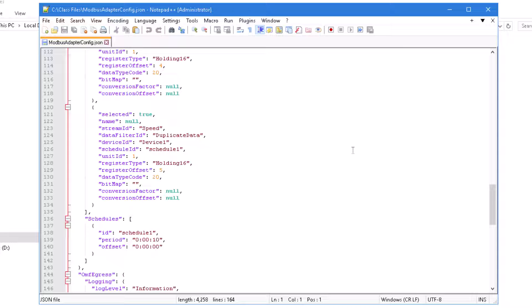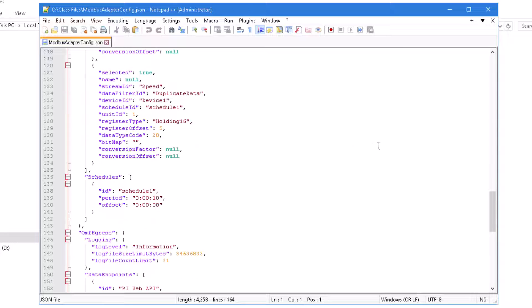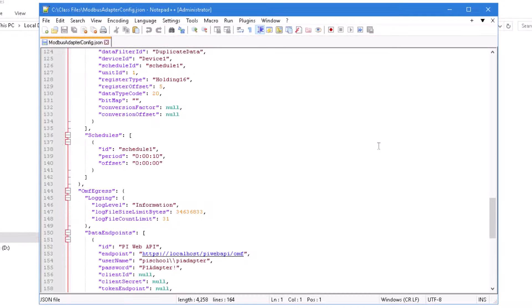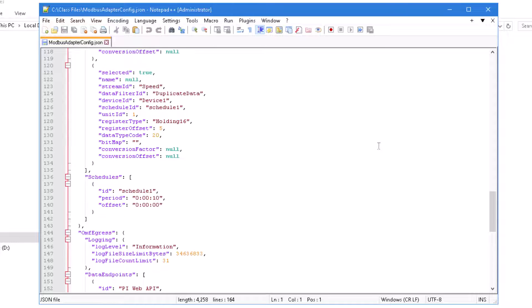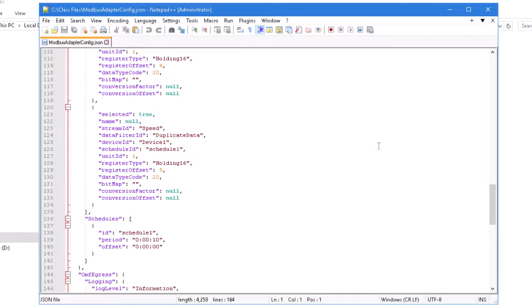Next, you'll see a data collection schedule specified with the ID Schedule 1, with a data collection period of 10 seconds. Each item in the Modbus adapter's data selection must be associated with a schedule. Schedules handle how often the adapter will scan for data.